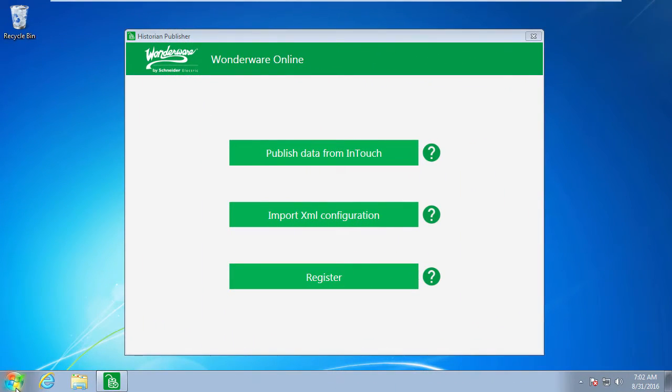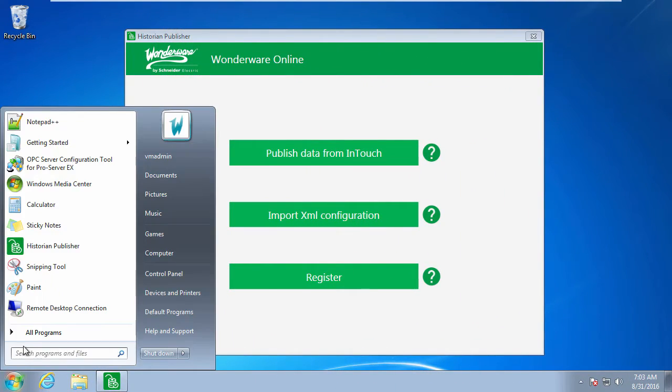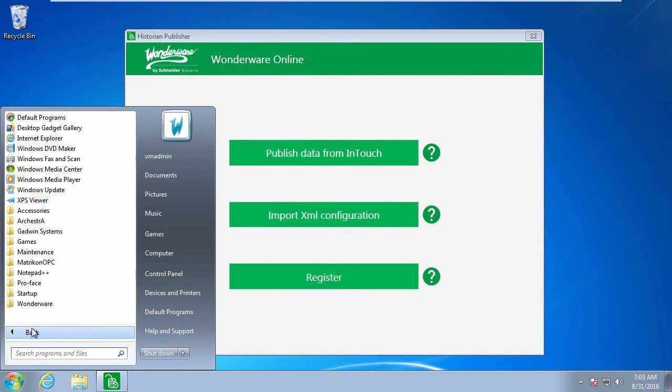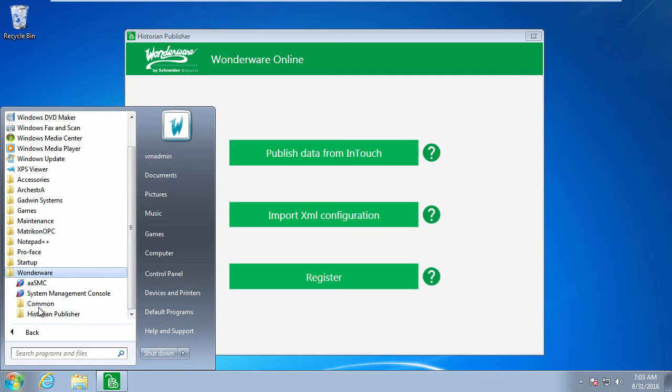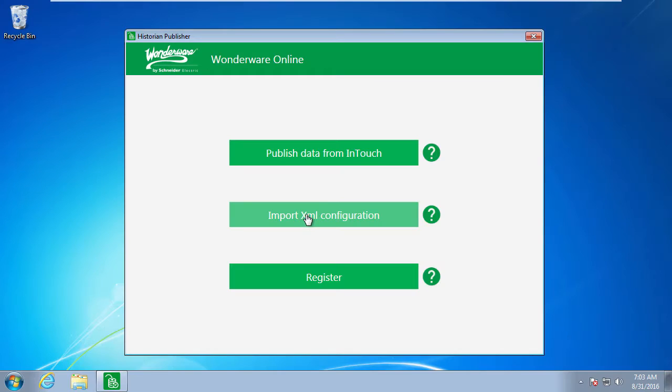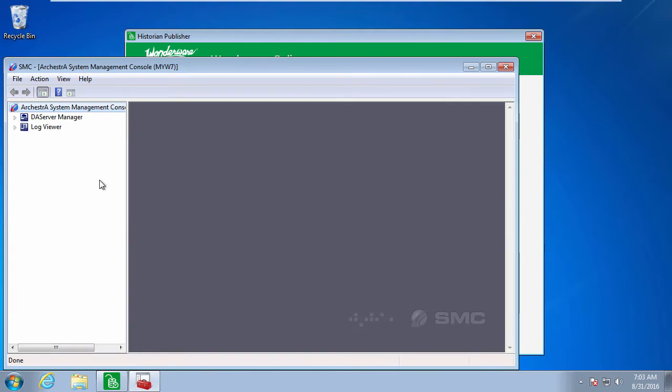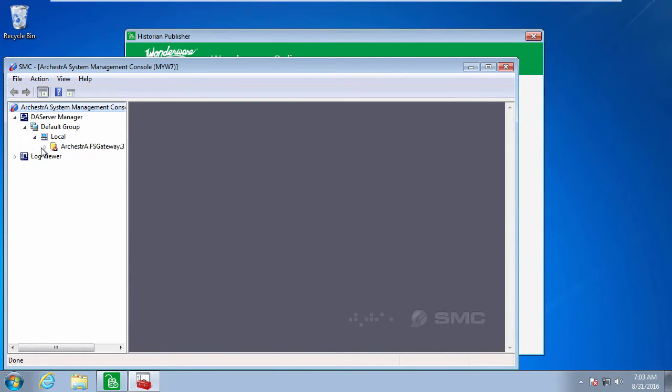Now, if I switch over to my PC that's actually running the OPC server, I've already installed the Historian Publisher, and I launched the System Management Console, and I have to do my initial configuration of what we call the FactorySuiteGateway. This is a one-time configuration.